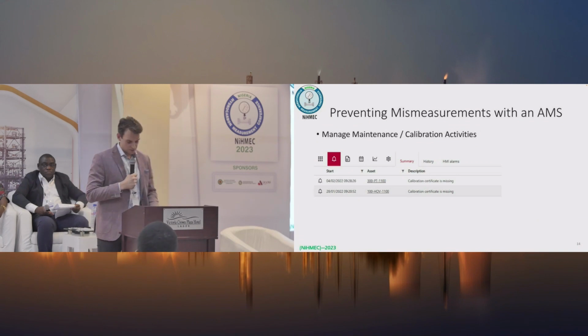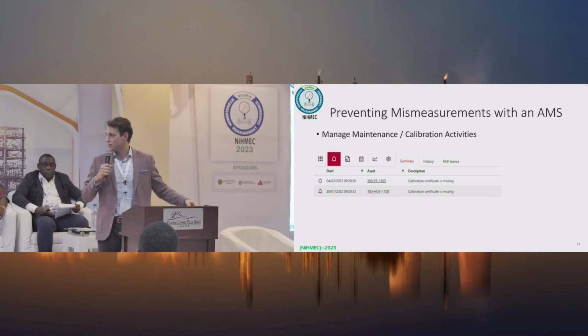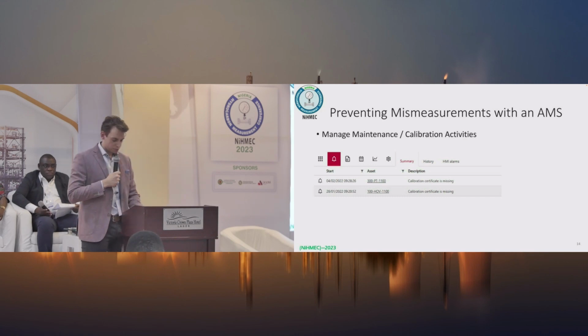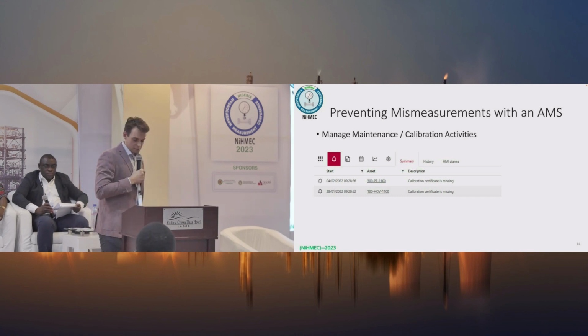You can also couple this and use it to schedule activities. For example, some calibrations - if you know a transmitter or flow meter has to be recalibrated every half year or every so many months, you can put that in the system, and the operators will see that they need to calibrate these instruments. You can also add step-by-step details so they can accurately perform the calibration without making potential errors. So you can actually put the operational procedures that are normally in writing into these types of systems.